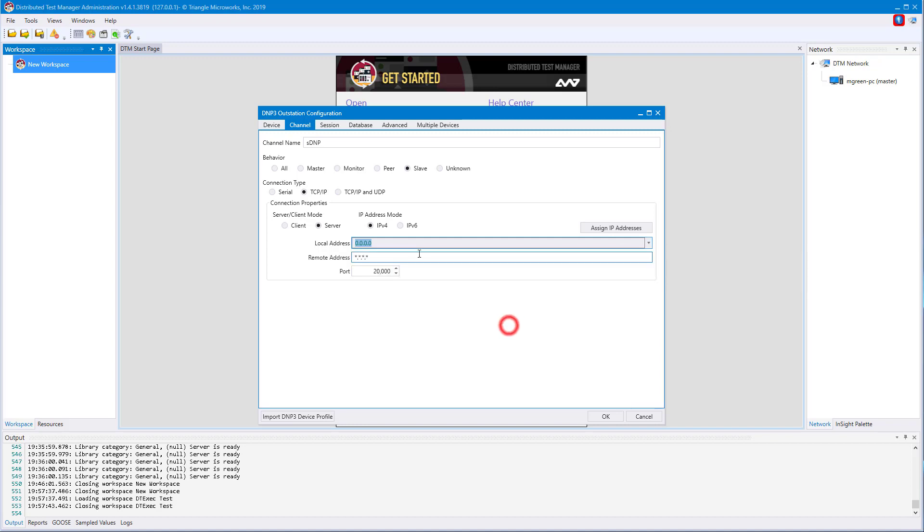You can also type in manually the remote IP address, or leave it as star dot star dot star dot star, which will allow anyone to connect to this outstation. The port number 20,000 is used by default in DNP3, but you're free to change it, especially if your DTM network does not have many unique IP addresses.